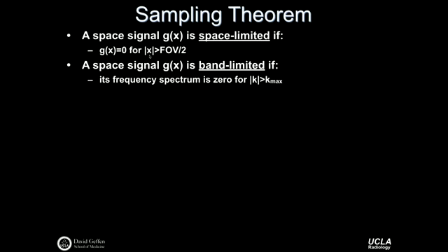And that's typical of the imaging experiments that we do. If your field of view is not appropriately sized, then you'll fall into this aliasing regime where those Fourier replicants will fold back into your image, and that will create artifacts for you that you don't want. So we're always good about specifying the field of view appropriately.